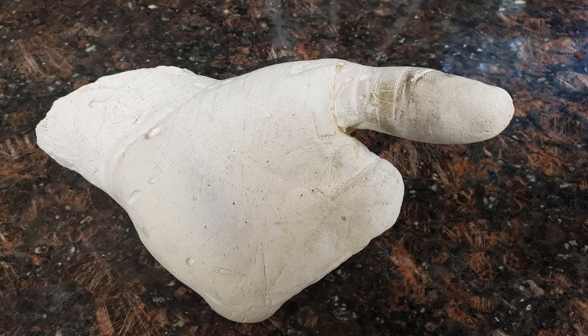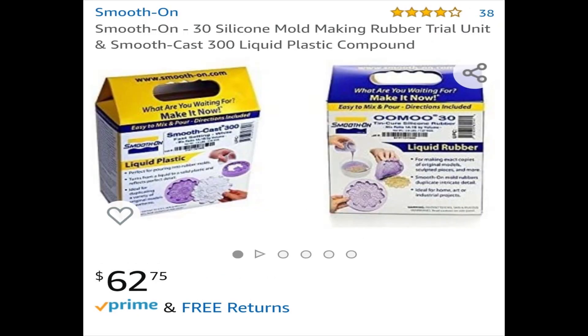Now there are of course a lot of ways to do anything, and this is just the way that I make the sockets for my prosthetic devices. I use these techniques because there is a really low overall cost of consumables compared to using alginate or silicone to mold the residual limb. On both wax and alginate, you only get one plaster out of the mold, whereas with silicone you can get three, possibly four, pulls.